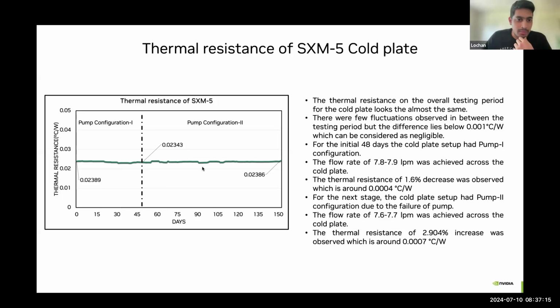Here you can see two different pump configurations in the graph. This is because initially, for the first 48 days of testing, there were two pumps connected in parallel, which gave a combined flow rate of 7.8 to 7.9 LPM on average. But after 48 days of testing, the liquid started leaking from the impeller, so we had to replace the pump with a new one. After the new pump was introduced, the flow rate dropped to 7.6 to 7.7 LPM, and we saw a small difference in the thermal resistance at that point. But overall, from day 0 to day 150, the thermal resistance is almost the same.